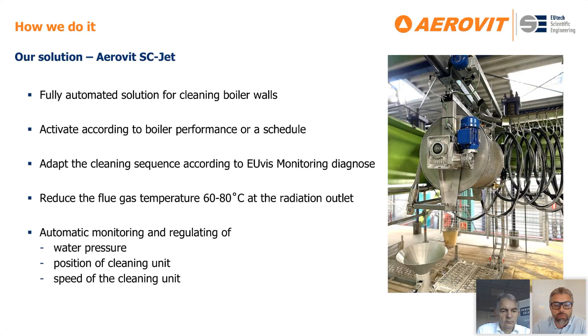Everything is automatically monitored and regulated, such as the water pressure, the position of the cleaning units, and the speeds. So you can segment your boiler into different parts, and then you can have a high speed of the cleaning in areas where you don't want to clean, and then a lower speed where you have more fouling. And again, this can be programmed according to the diagnostics you have from the EUtech monitoring. Again, as I said, you get a higher boiler availability. We have customers running a full year without any stoppage.